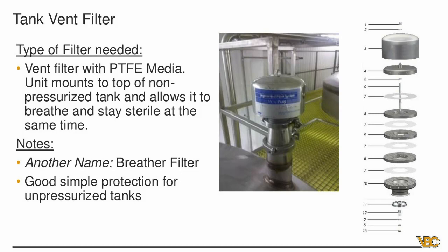These are not sized based on how big your tank is, but on how much your tank is flowing. Even if your tank is 30,000 gallons and you have a very low flow, you would have a very tiny filter. So it's not something where you need a massive filter for a massive tank. It's really based on the flow.